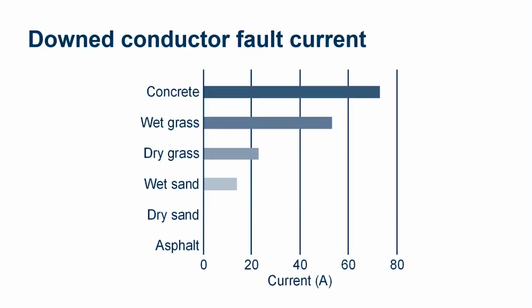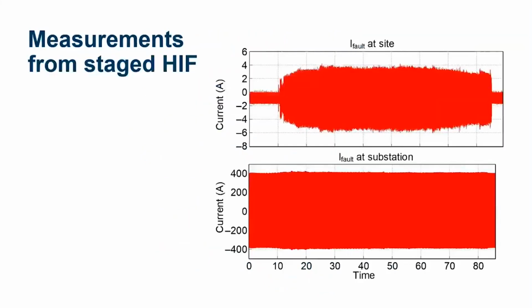So this gives us an idea of what we mean when we talk about a down conductor and high impedance fault. This is again from another staged test, and we can see that in this high impedance fault we have very little fault current, and it's difficult and practically impossible to pick out this high impedance fault if we're just looking at the total RMS current magnitude back at our substation. So in many cases, our traditional protection is going to be insufficient.